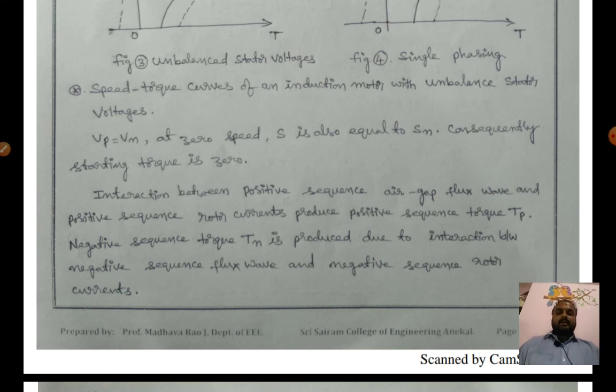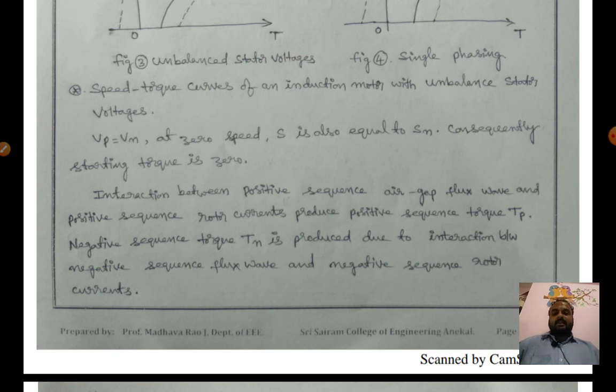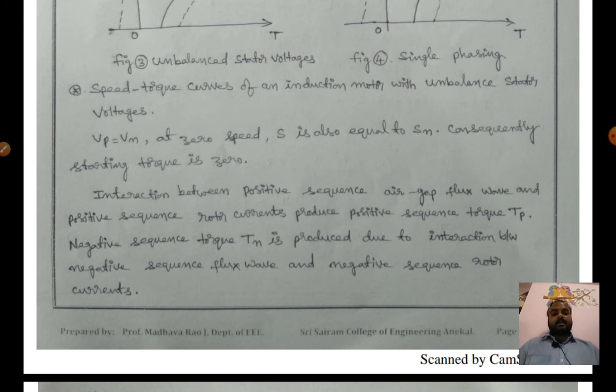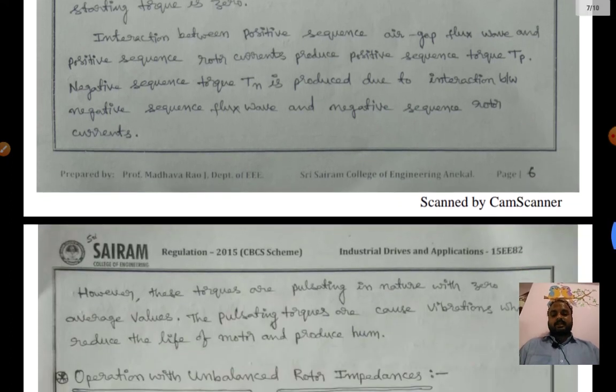Interaction between the positive sequence air gap flux wave and positive sequence rotor current produces positive sequence torque. Similarly, the negative sequence torque Tn is produced due to interaction between the negative sequence flux and negative sequence rotor currents, resulting in torque in the negative (braking) direction.